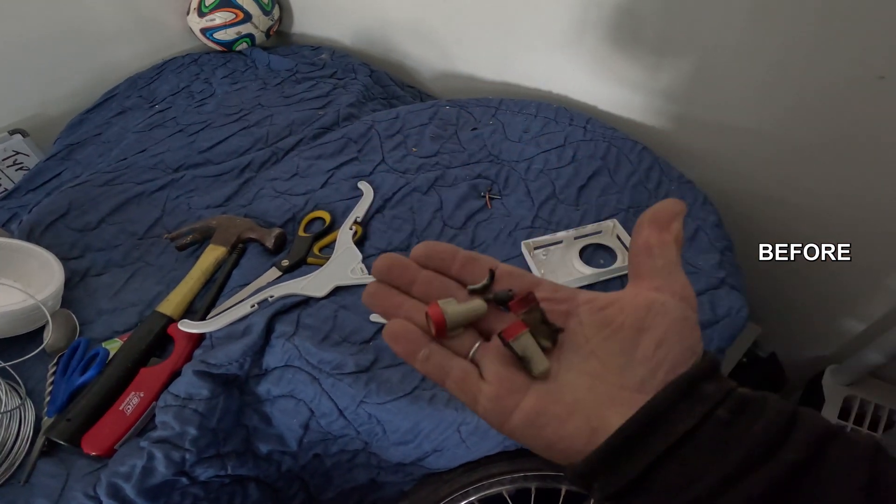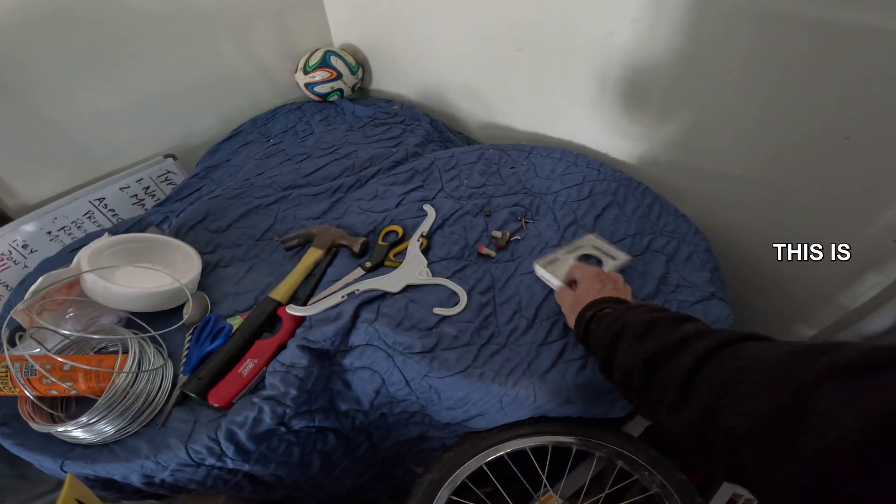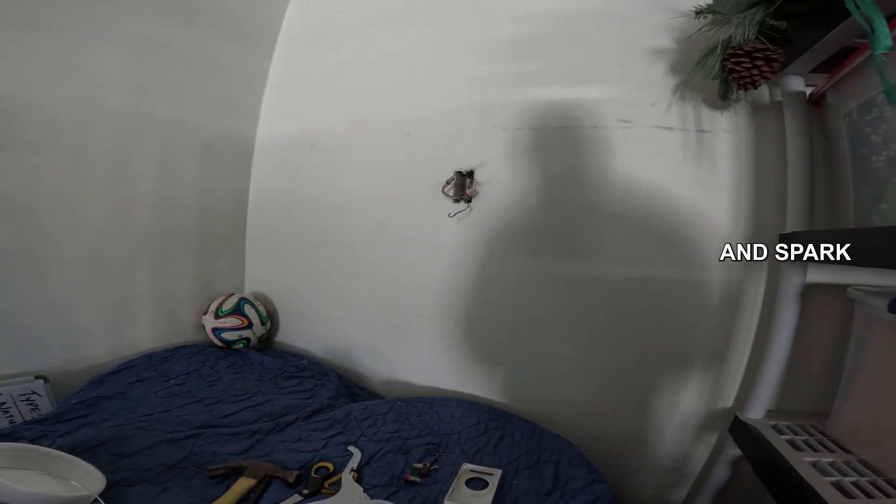You'll see this is what we found when we got here. Just because of the loose connection up there in that thermostat location, it caused the wires to arc and spark.